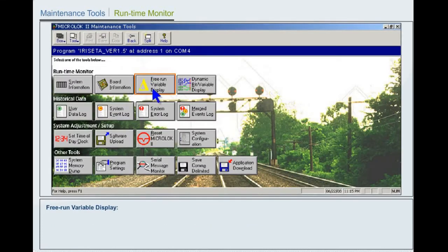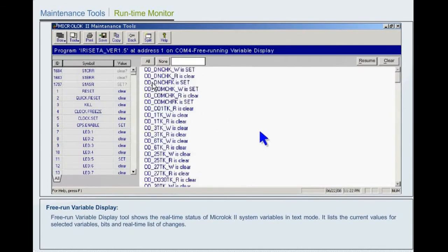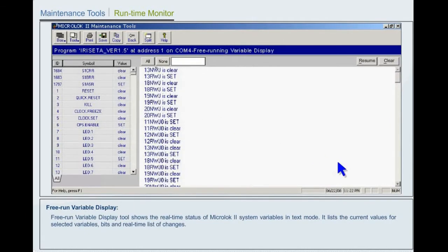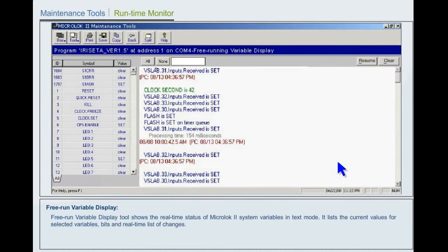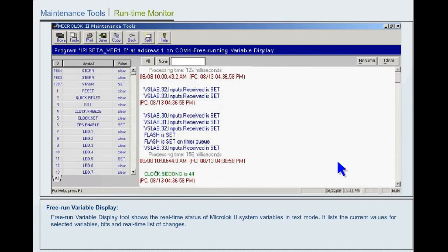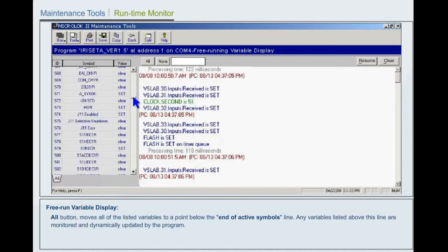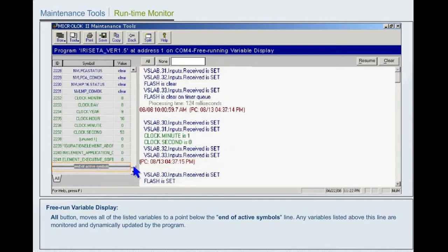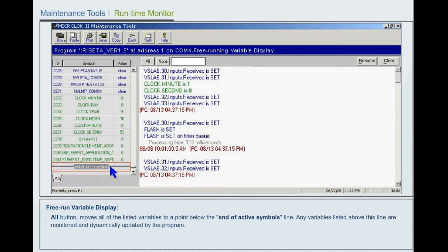Free Run Variable Display. The Free Run Variable Display tool shows the real-time status of Microlok II system variables in text mode. It lists the current values for selected variables, bits and a real-time list of changes. The All button moves all of the listed variables to a point above the end of active symbols line. Any variables listed above this line are monitored and dynamically updated by the program.